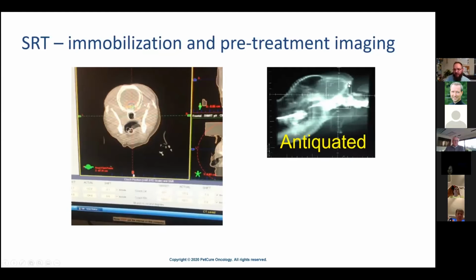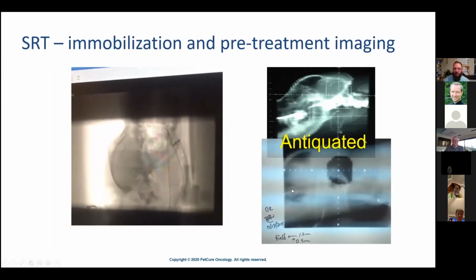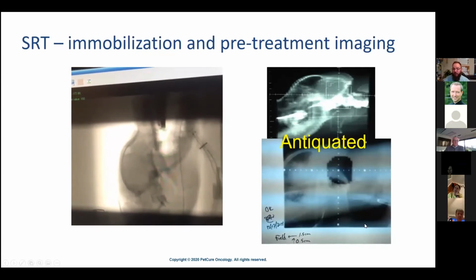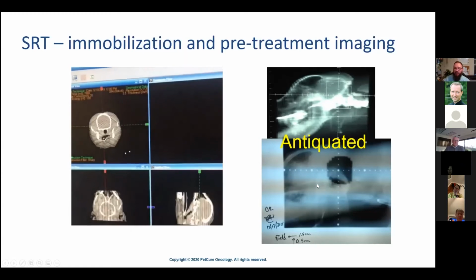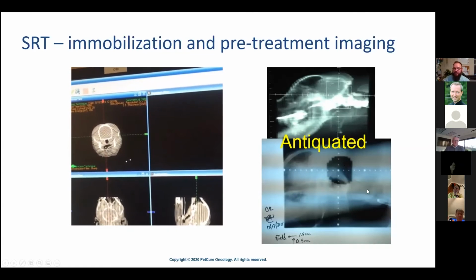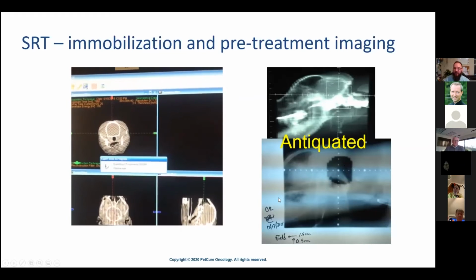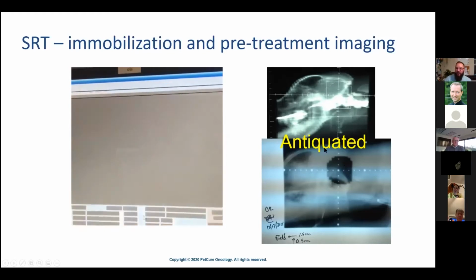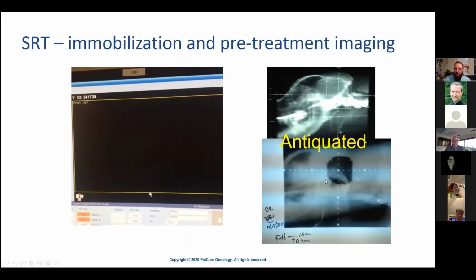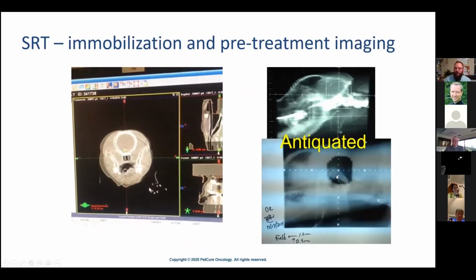This is actually an image from my residency. So this was a dog with a brainstem tumor. You can see the multi-leaf collimator leaves in this beam's eye view. You can see them actually cut out in this image. This is what's called a digitally reconstructed radiograph. So this would be basically a radiographic image off of the planning CT. And then what we had here was actually radiographic film. So this would be an image that we would take while the patient's on the table. We'd run across the hospital, develop it in our developer, and then take it back to the control room and look in a light box and compare these two images to make sure that we were, the best we could eyeballing, the accuracy of the beam placement.